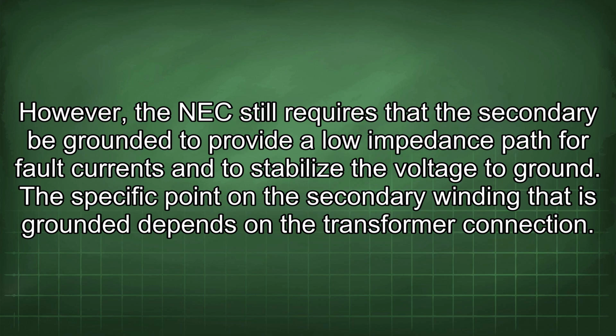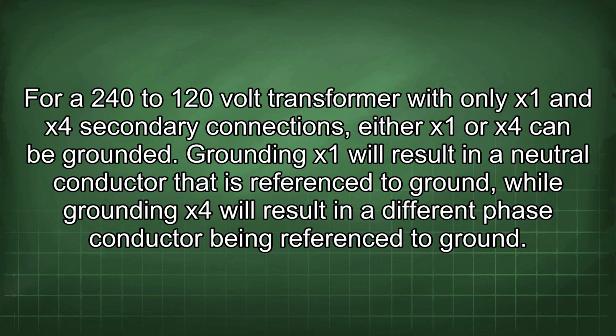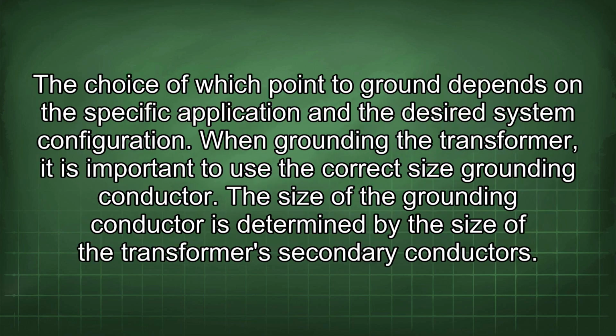The specific point on the secondary winding that is grounded depends on the transformer connection. For a 240 to 120 volt transformer with only X1 and X4 secondary connections, either X1 or X4 can be grounded. Grounding X1 will result in a neutral conductor that is referenced to ground, while grounding X4 will result in a different phase conductor being referenced to ground. The choice of which point to ground depends on the specific application and the desired system configuration.